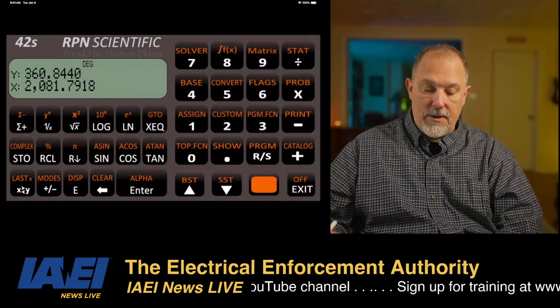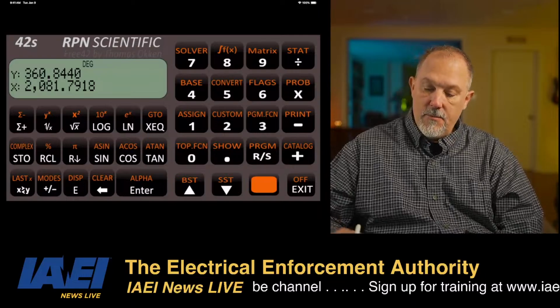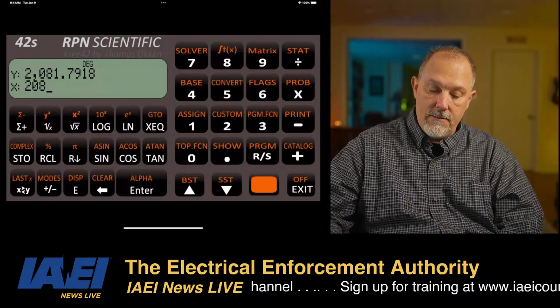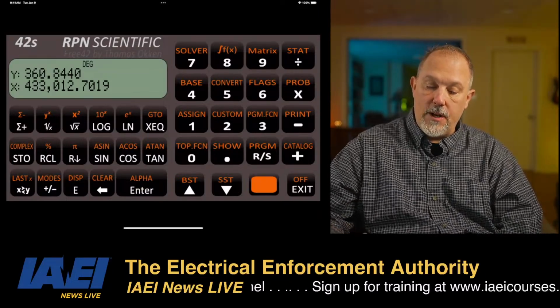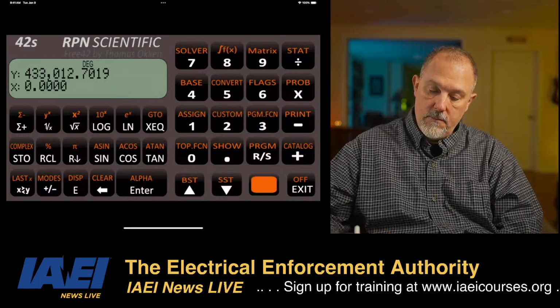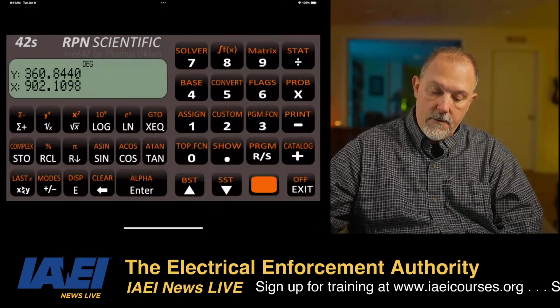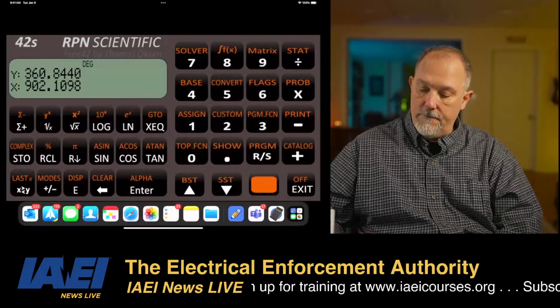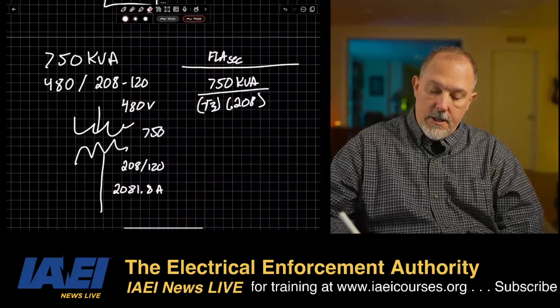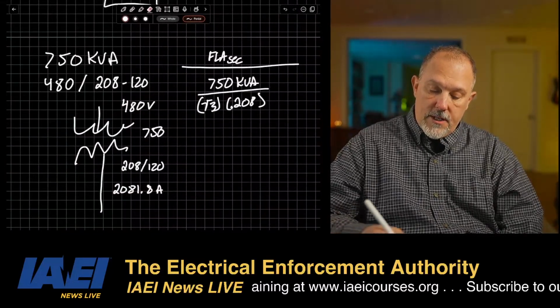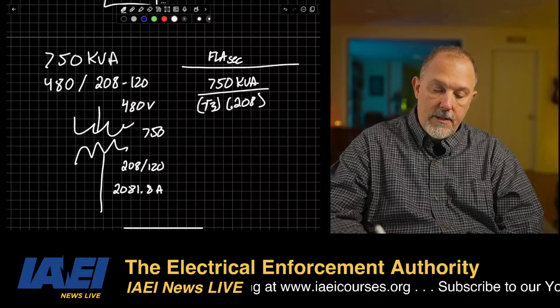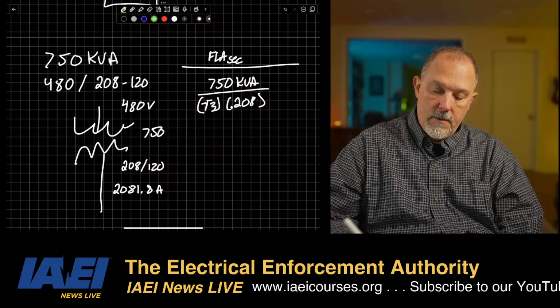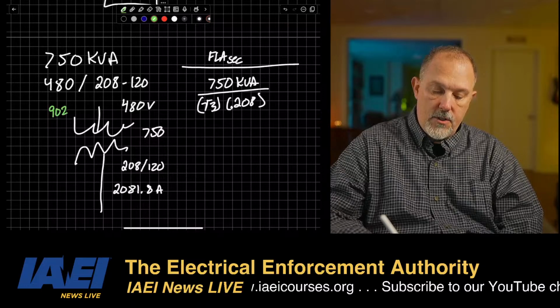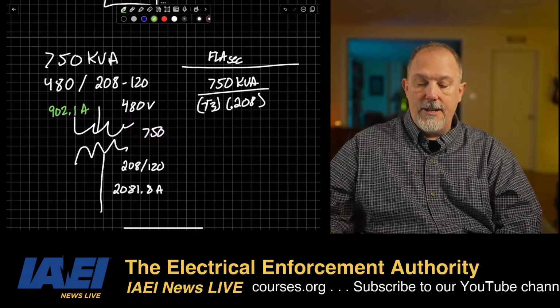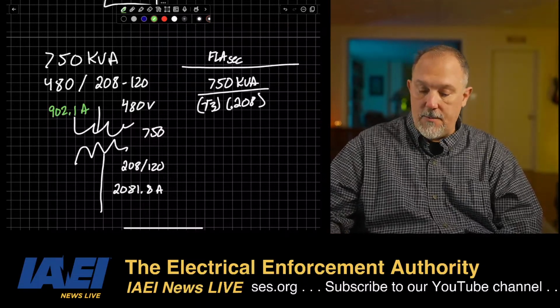Now, if I want to know the primary current, I take 2081.79 or 2081.8, multiply that by 208, divide that by 480. That's 902.1. So the primary is 902.1 amps.